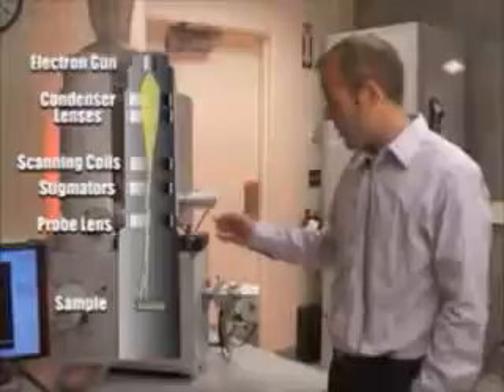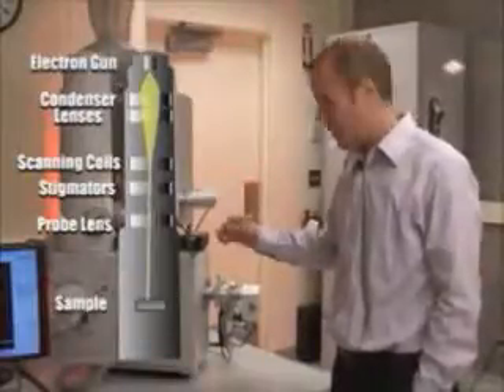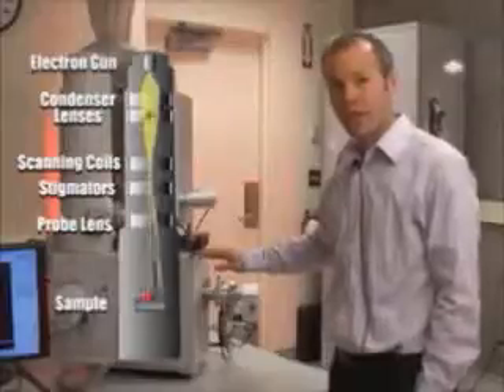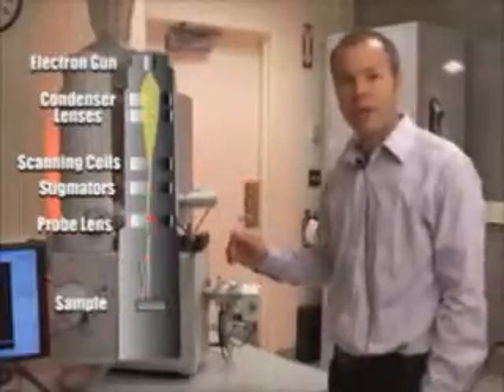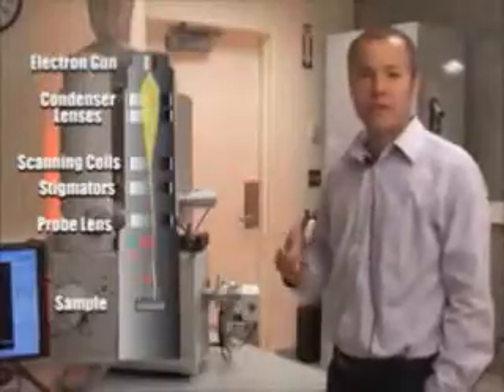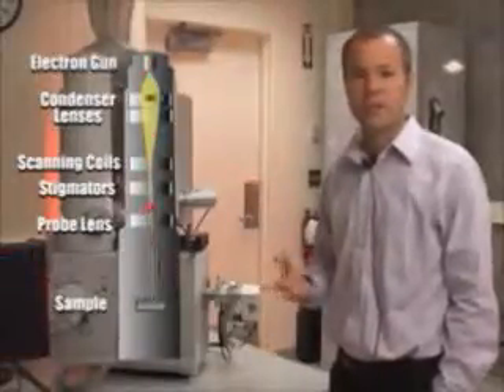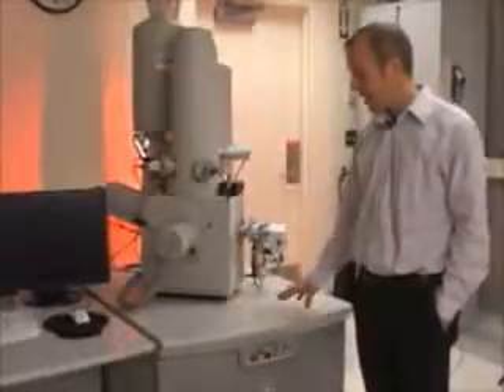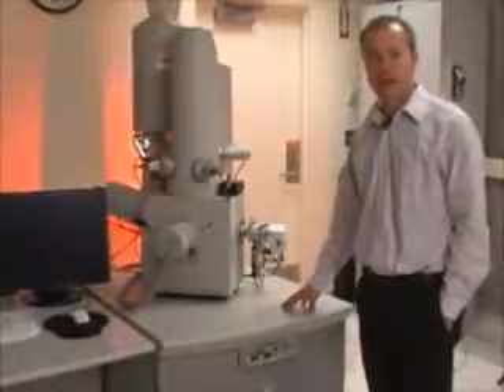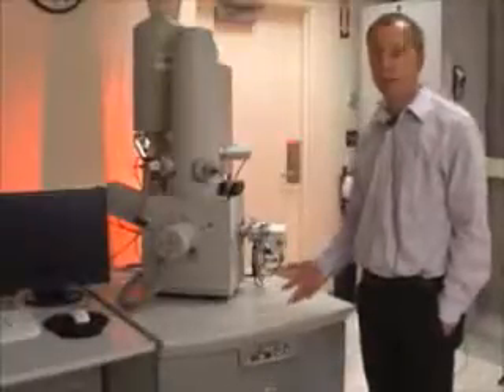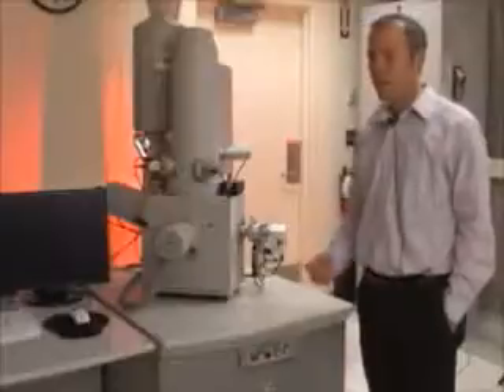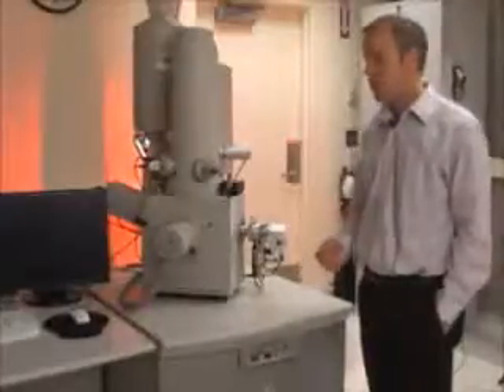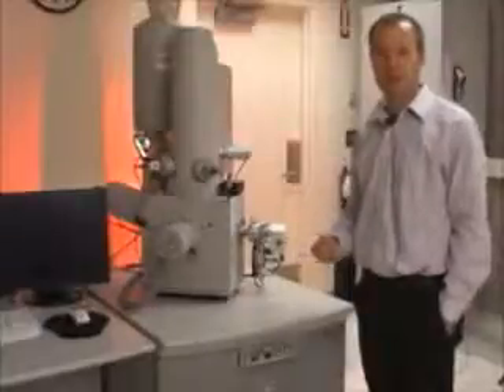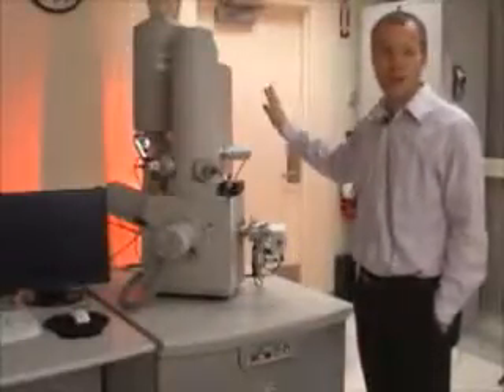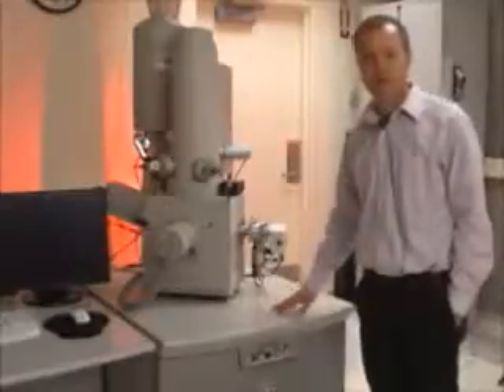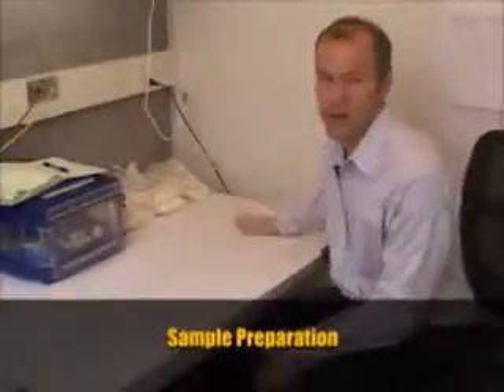When the probe, the electron beam, exits from the probe lenses, it then enters the chamber, which is the square section here, and it impacts the sample, where the sample absorbs the energy of those electrons and then re-emits new signals that we use to image the sample. You'll also find inside of the table there's a turbo pump that actually helps pump the chamber down to high vacuum. The chamber pressure is on the order of 10 to the minus 5 millibar. There are two different pumps used to pump the chamber down to that level. The main pump is located in the adjacent closet that you don't see, and then the turbo pump is in this table here. The sample preparation happens in this area here.